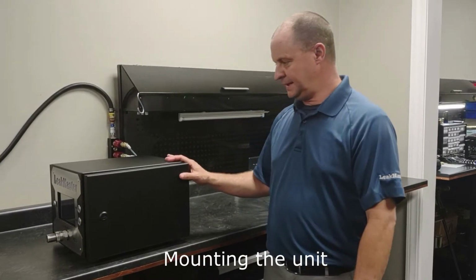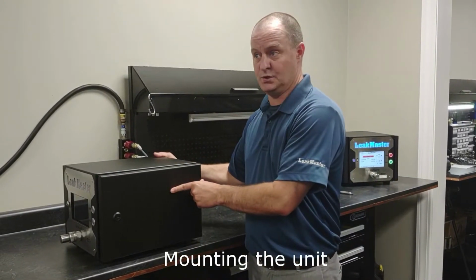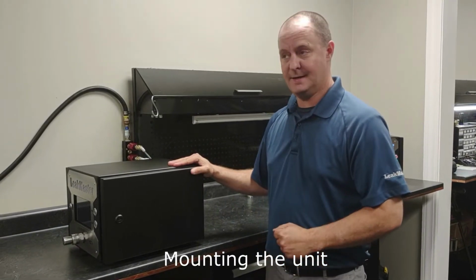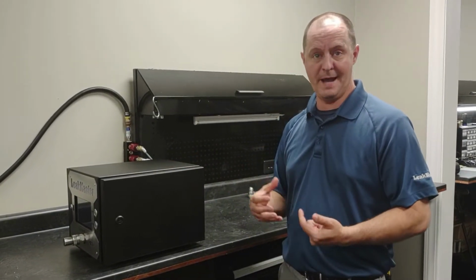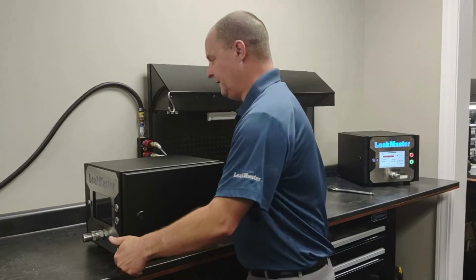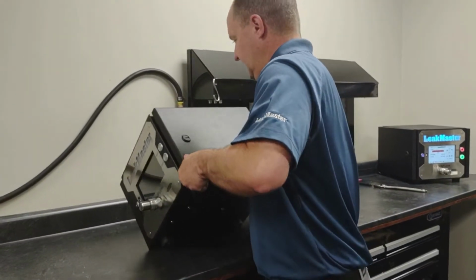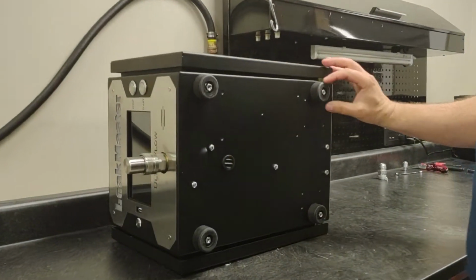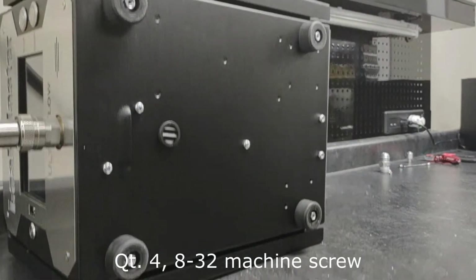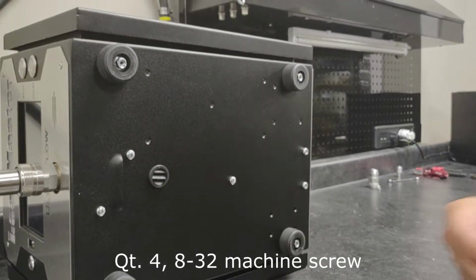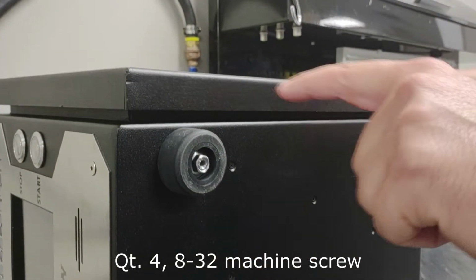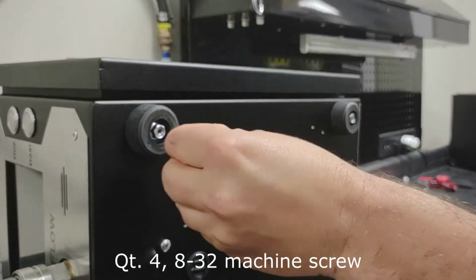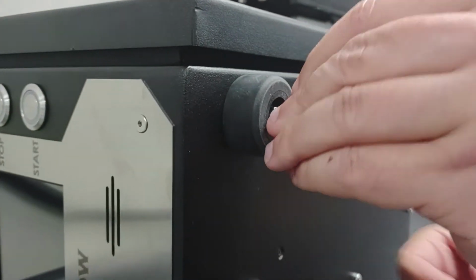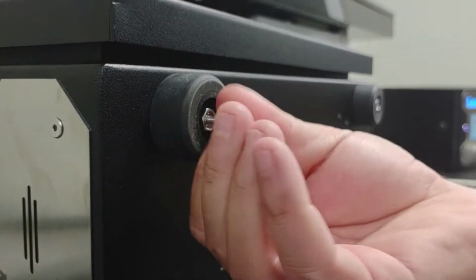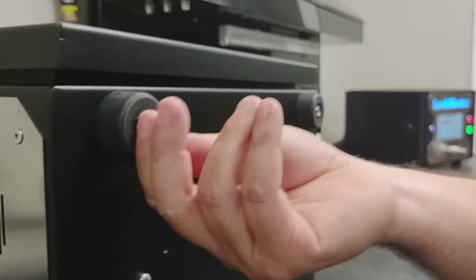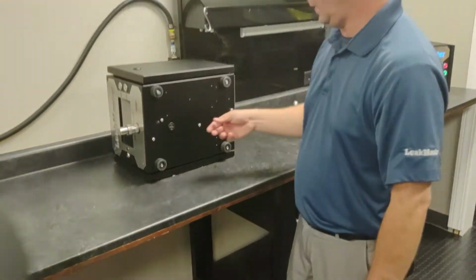Now the UltraFlow unit can just sit on an actual shelf, like it's sitting right now, or you could firmly mount it down with bolts as well. If I flip this over on its side, you will see that the mounting feet right here have bolts holding them in, but these bolts are also threaded for 8-32. So if I had a plate with properly spaced out holes, I could go through that plate and lock this down with an 8-32 bolt times 4.